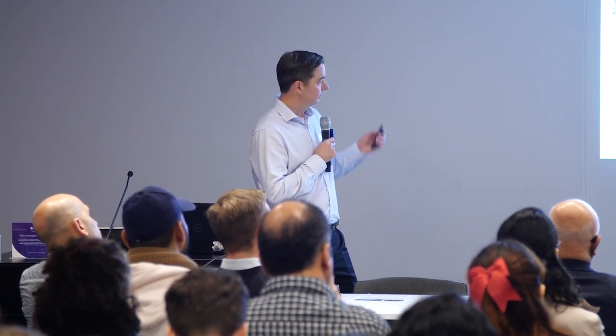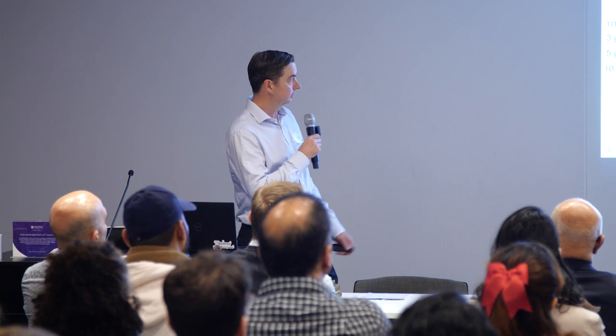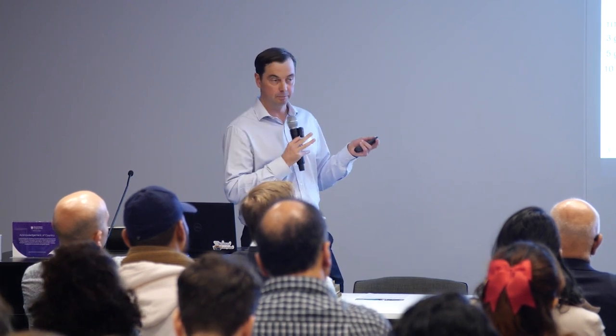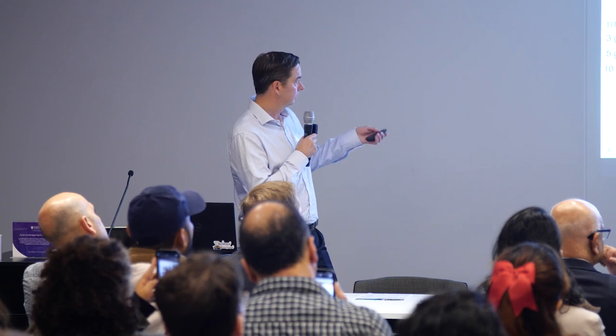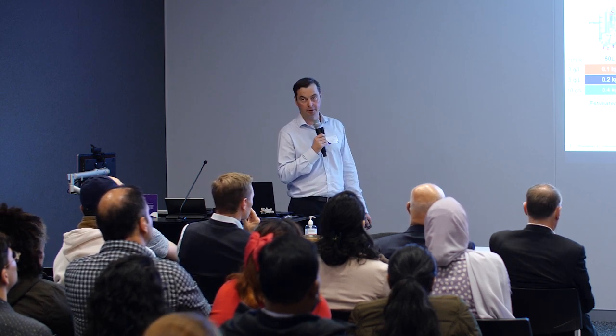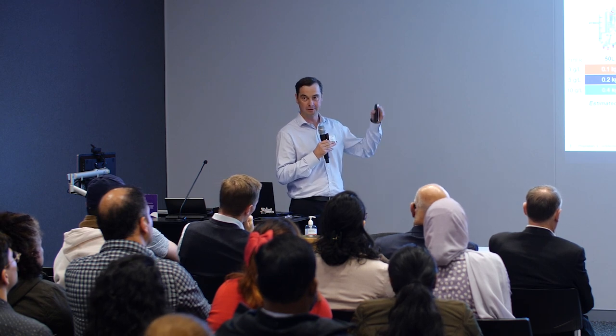With that in mind, Thermo Fisher has focused on bioreactors up to 2,000 litre scale for clinical and commercial antibodies. But if we're predicting towards 400 kilos per year, we need something bigger. Thermo Fisher has recently released the next size up in the single-use bioreactor — a 5,000 litre bioreactor known as the DynaDrive. Product coming through now ranges between 10 to 40 kilos per batch depending on titer, so at 400 kilos per year you need 10 to 15 batches a year — that's the reason for investing in this 5,000 litre scale rather than staying at 2,000 or jumping to 10,000–20,000 litre stainless steel.